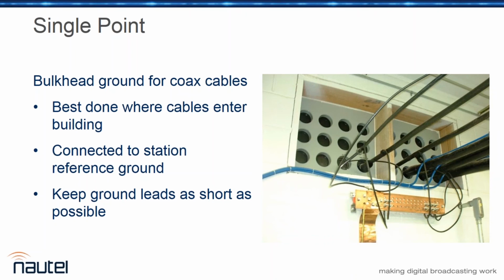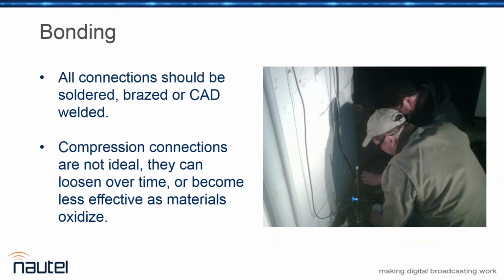Exactly. So definitely keep the ground short, keep them straight. We like to see them bonded, preferably soldered. Well, I like CAD welding. Where else do you make something go boom on purpose? You put a ceramic mold around your ground rod and the cable going to it, touch it off, it goes boom, and now you've got a permanently exothermic connection. The problem with CAD welds is you have to have a different mold for every different type of connection. And unless you're willing to invest $400 or $500 in molds, whatever you've got is going to be not the one you need.